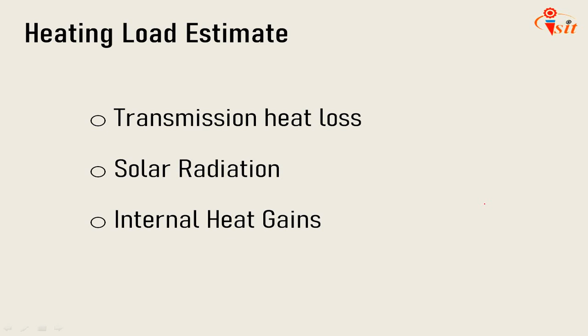Now, solar radiation. What is the effect of solar radiation on the sensible heat and latent heat loads? That we are going to see now. The solar radiation intensity normal to the sun rays incident upon a plane surface situated in the limits of the Earth's atmosphere varies with the time of the year as the distance of the Earth from the sun changes. Its value when the Earth is at its mean distance from the sun is called the solar constant. The normal value of the solar constant is assumed as 5045 kilojoule per meter square hour.